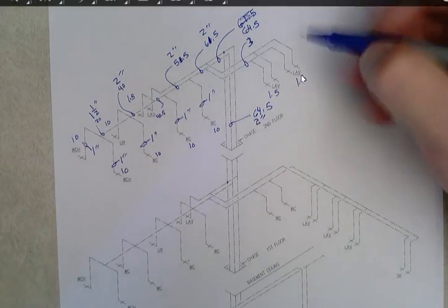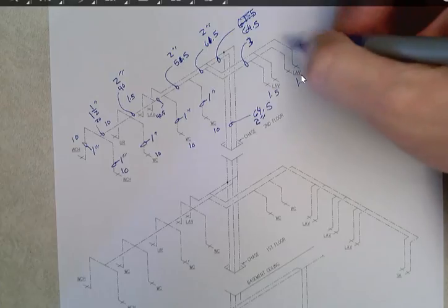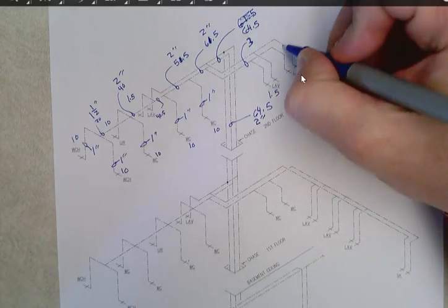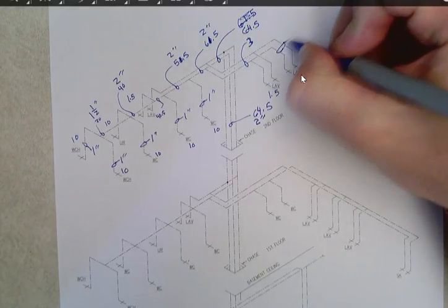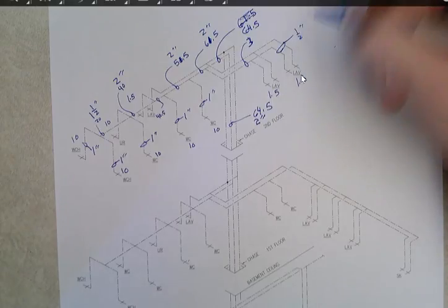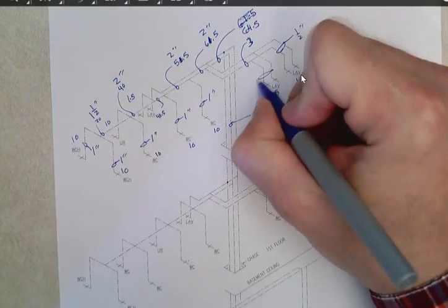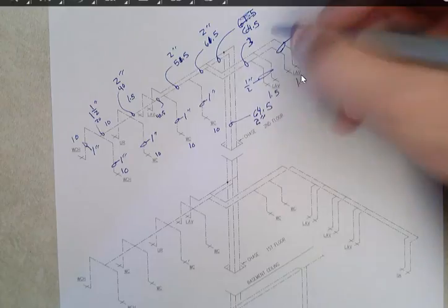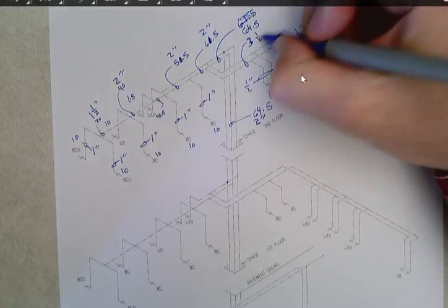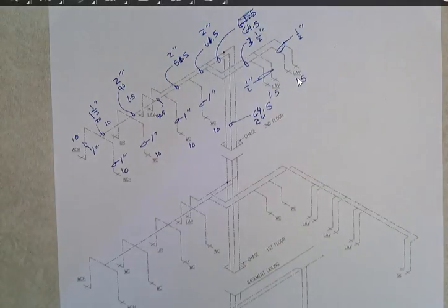So whenever I look back here, I can go ahead and write my line sizes on. I'm just going to go ahead and make those a 1/2 inch. I'm going to go ahead and add the hot water also, because I know there's the same fixture units, and I'm using the hot water or flush tank chart now. So I literally have a 1/2 inch line size the whole way throughout for my hot water system and on the right hand side with my lavatories.